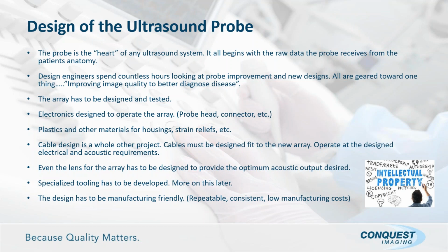Cable design is a completely different project. Again, it's got to be able to fit and connect to the interconnect on the array. Sometimes that's done by individually soldering every microcoax wire onto the array. Sometimes it's done with flex circuits, and sometimes it's micro connectors and things like that. It just depends on what the engineers come up with to optimize their design. The cable has to work electrically, but also make sure that acoustically it's not got a lot of signal noise problems or signal loss. So those things all have to be factored in.